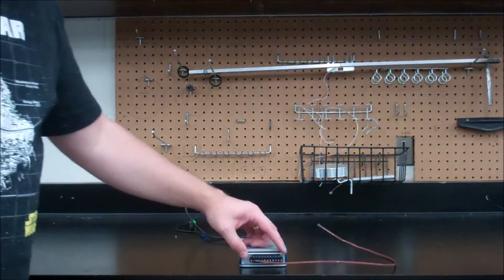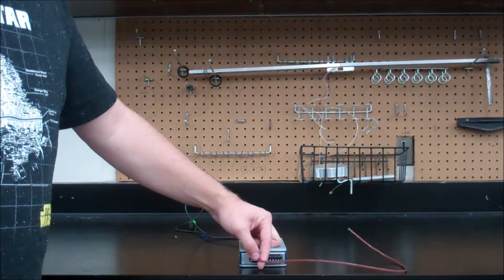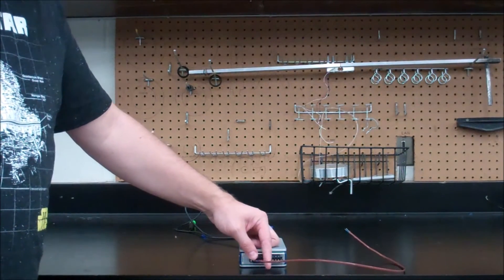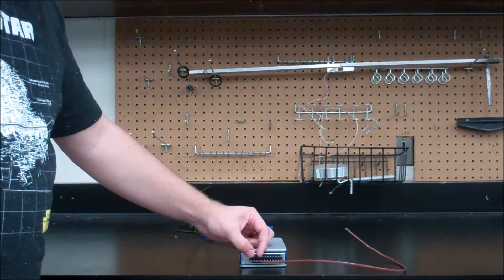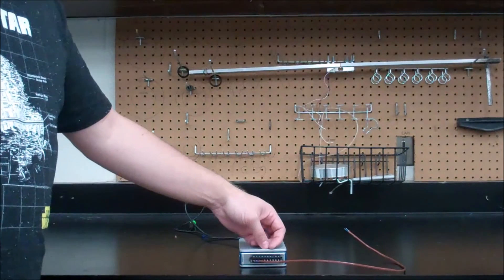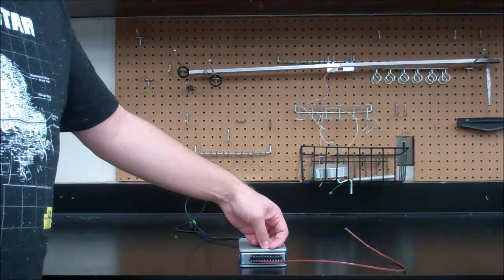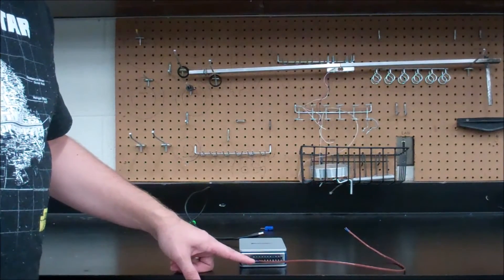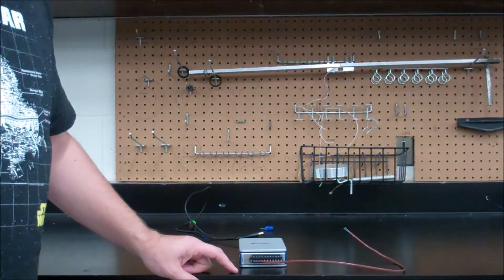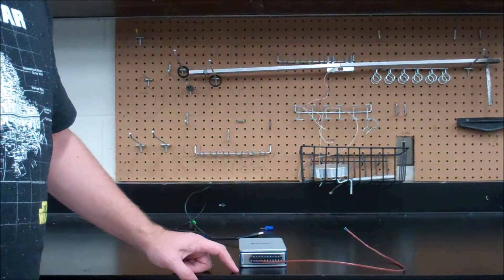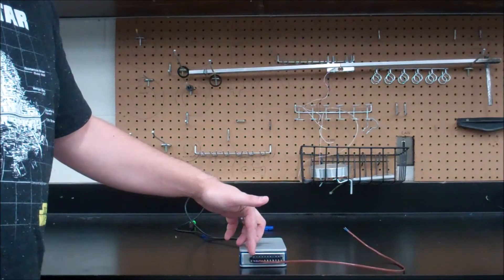So again, if you have a different type thermocouple like a K or a J type and not a T type, you can look up what's the positive and negative cable coloring. And if all else fails and you can't figure that out, then just connect the thermocouple, run your DAQ, see if you get the correct temperature. If not, then flip the wires, flip the polarity. So if you plug in, say you put the copper in zero and the silver in one and you're not getting the correct temperature, then flip the copper to one and the silver to the zero port.